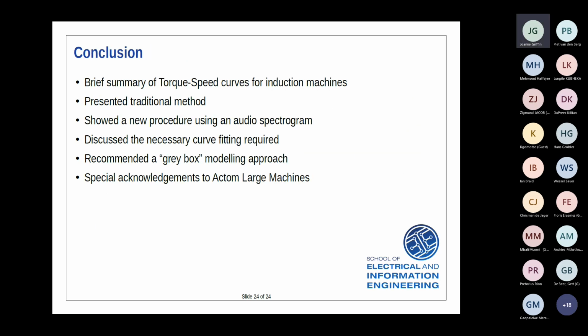Just to conclude: we were looking at torque speed curves for induction machines. I showed you the traditional method using a handheld tacho generator, which has been around for decades - very simple, but it has its problems, hence we explored this new idea of using an audio spectrogram. The problem is that you can't get data close to zero speed, where you really need it for the locked rotor torque. That brings in a need for some curve fitting to estimate what happens where there's no data. What I'm suggesting is that with some grey box modeling, if we know some detail about the machine already, we can accurately predict where the curves will fit the best maps through the data.